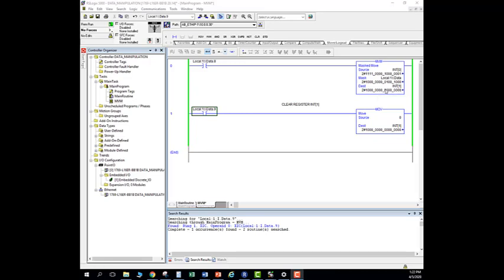If I take away that mask, that number 16 bit, and so now that bit is masked out, and I trigger this MVM again, what do you think is going to happen? Do you think it's going to zero that out? Is it going to move a 0 in that location, or is it going to keep it a 1? Now it's masked. It's not going to transfer any information to this location because it is masked. Watch this here. Triggered, no change in state. It still stays a 1.